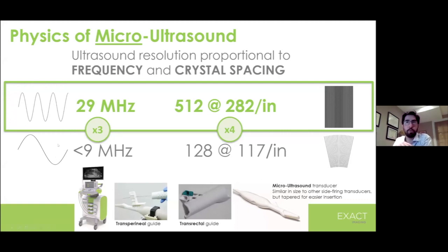But we don't just image better in frequency, we also image better in terms of the number of crystals in our ultrasound transducer and in how they're packed. Most ultrasound transducers out there have about 128 crystals, spaced at about 100 per inch along one of these curved arrays. We have 512 crystals in our transducer, spaced 2 or 3 times higher. And instead of being a curved surface, our transducer's flat, which means the lines stay perfectly parallel as they go deeper into the prostate, whereas the lines of most other transducers diverge, and that makes it difficult to image the deeper structures.